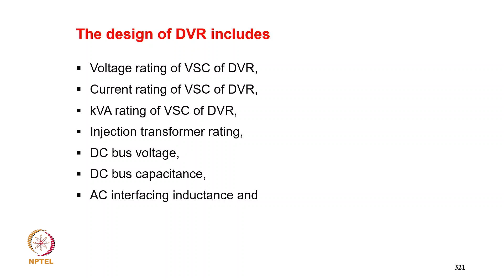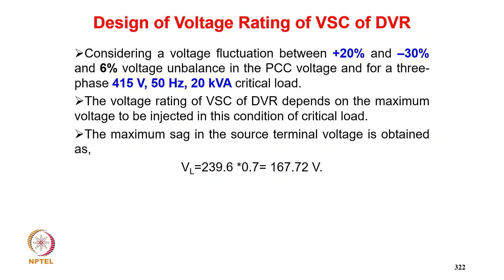Coming to design of voltage rating, considering a voltage fluctuation of plus 20% and minus 30% with 6% voltage imbalance, in a 3-phase 415 volt 20 kVA critical load. So the voltage rating of the VSC of DVR depends on the maximum voltage to be injected in this condition of critical load. The maximum sag in the source terminal voltage is obtained as VL equal to 239.6 into 0.7, that is 167.72 volt.